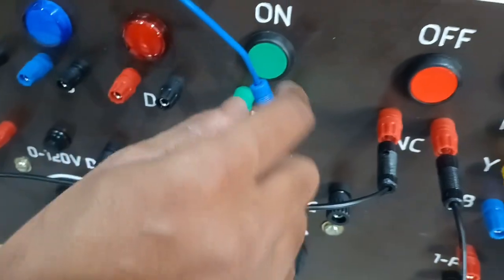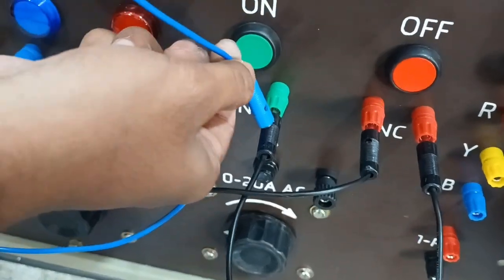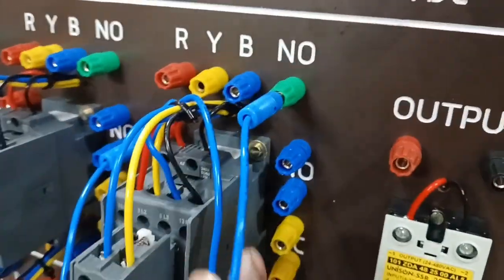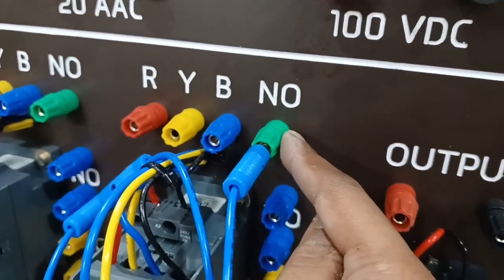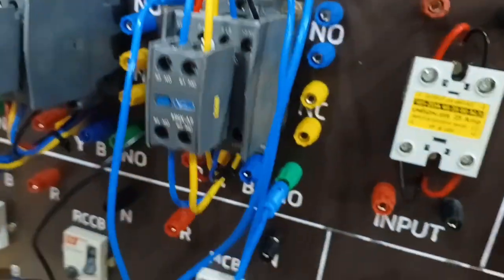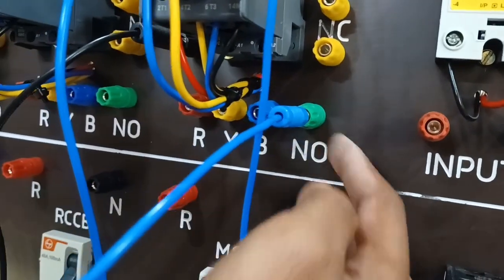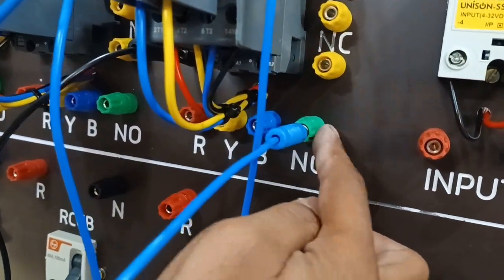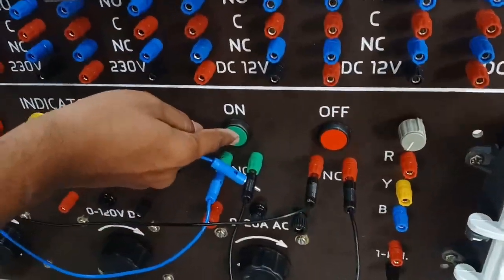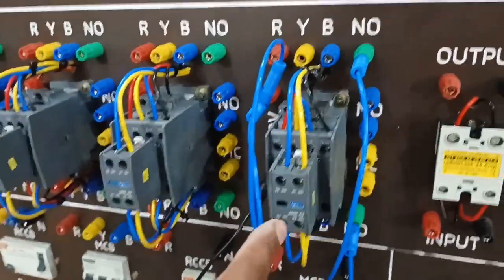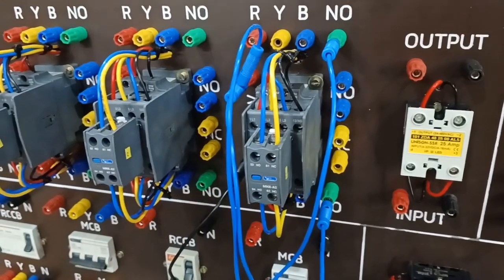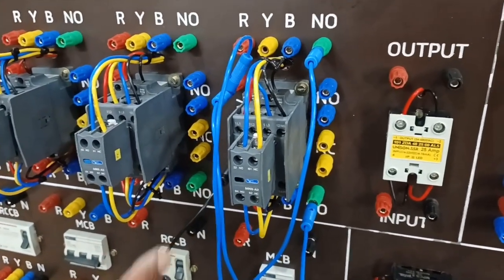And take one more patch cord, connect here, the NO terminal phase connection, and this is connected to the contactor NO terminal. Again from the contactor NO terminal to the contactor coil. This is the contactor latching connection. Now you just press this green button and look at the contactor. This is the contactor operation.